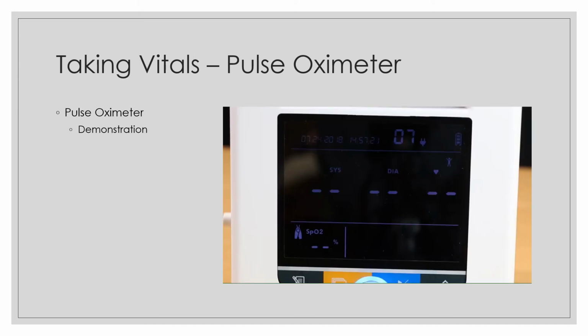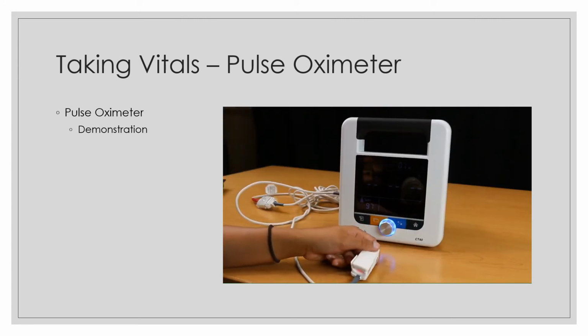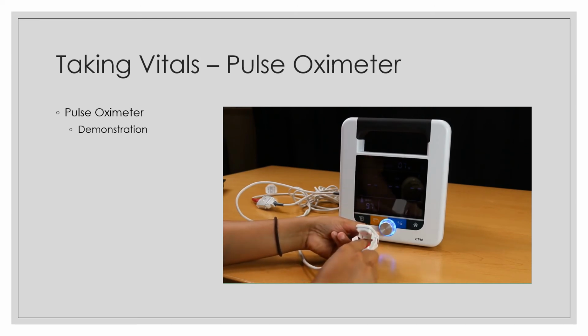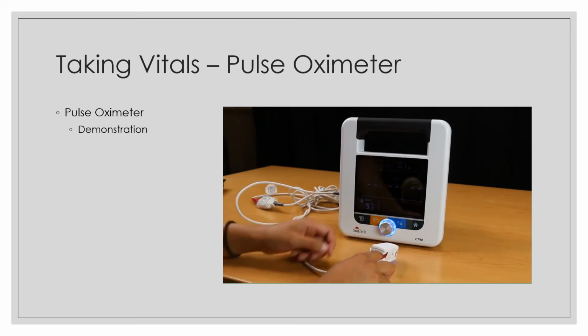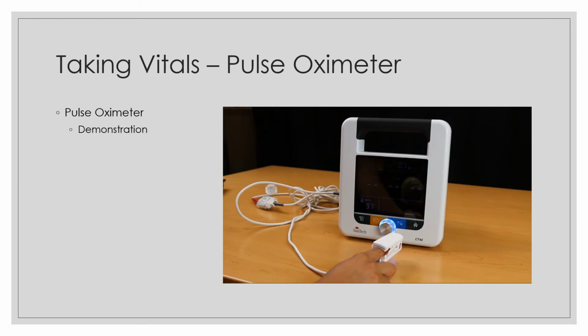After a few seconds, an SpO2 reading is displayed on your CT40 display screen. Remove the finger from the SpO2 sensor to display the last measurement. To start a new measurement, reapply the SpO2 sensor to the patient's finger and follow the same instructions as before. If you do not remove the sensor from the patient's finger, the SpO2 readings will stop automatically after 10 minutes of continuous measurement. The last measurement will be displayed on the screen.